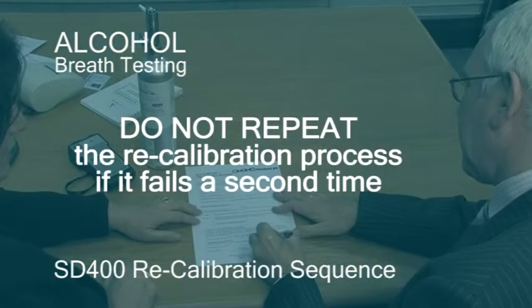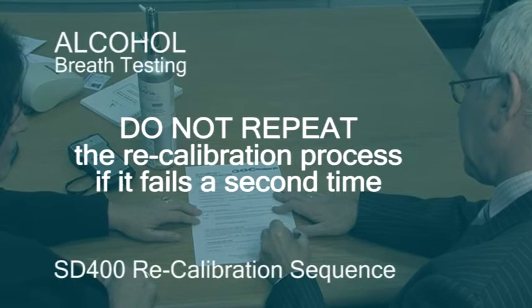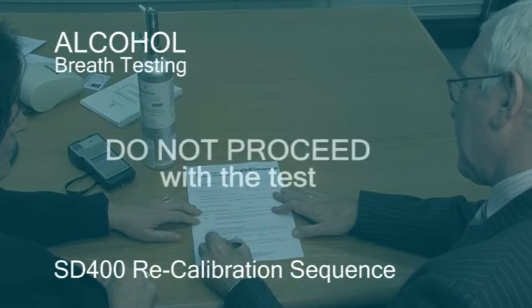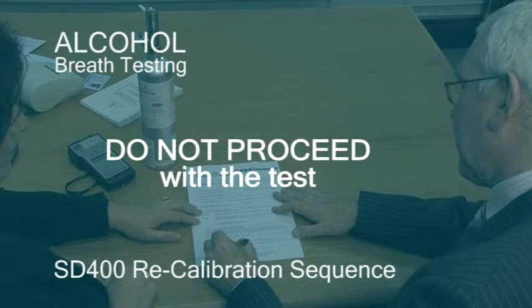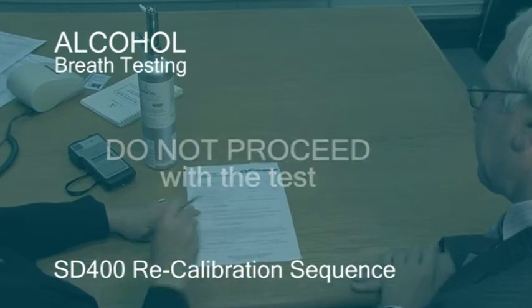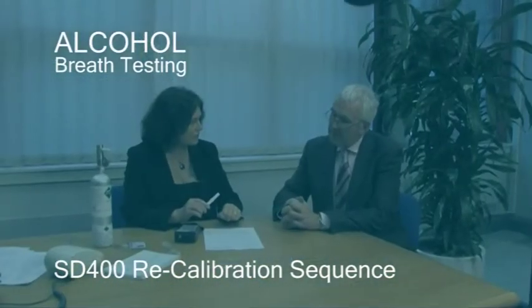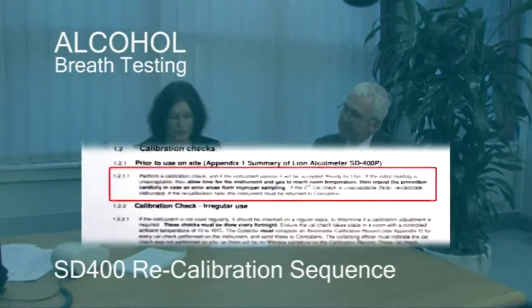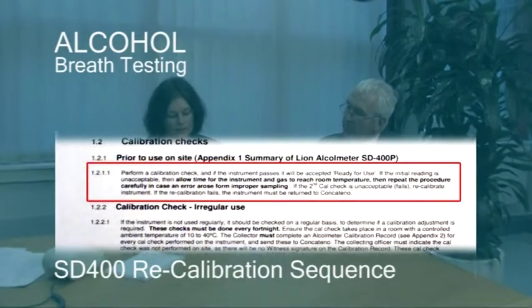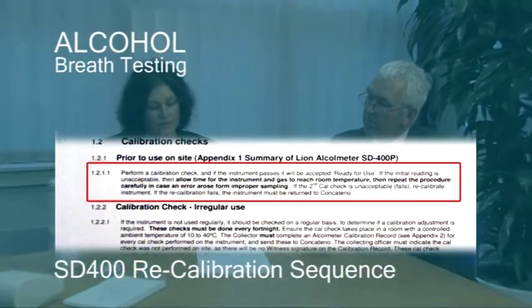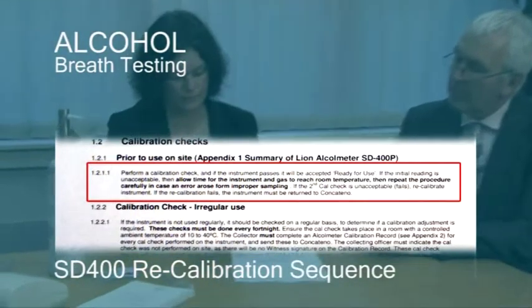Do not repeat the recalibration process if the calibration check fails again, and do not proceed with the test. Your machine must have a fault, so please contact us. You will be given instructions on what to do about collecting an alternative specimen. If the machine is working properly, you can proceed with the breath test.